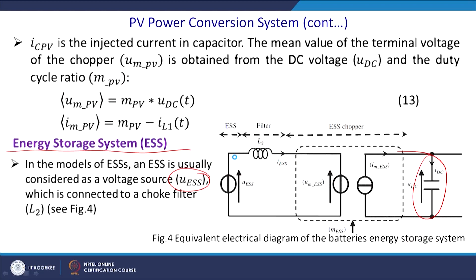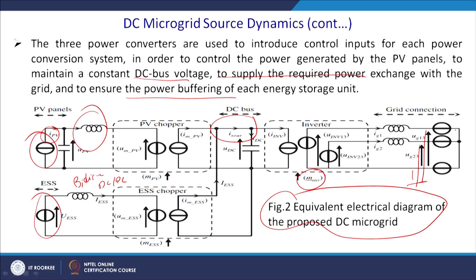Now, this is IPV, and this is UPV, and ultimately this is your PV chopper part. Here you have an inverter, where your modulation index comes into the picture, and from this modulation index you have this inverter connected to the system, and you are injecting power into the system. Thereafter, this is your energy storing element, which is essentially a bidirectional DC to DC converter. When you have surplus power, it will store it, mostly in the battery, and it will take out power once there is an energy deficiency in the local grid. Most of this model is generally coupled with local resistances or a local load, then only the analysis will be complete. Sometimes we will provide a load here before the connection to the grid, so that it can also operate in the islanding mode.